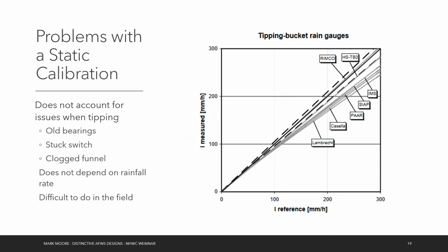There are some problems with static calibrations. For example, it doesn't account for the fact that you lose a certain amount of rainfall when the bucket's tipping. And so if you've got old bearings in there, it's not caring about how long it takes between tips. All it's caring about is how much rain does it take to tip. It's not going to tell you anything if your funnel's clogged or if you've got a stuck switch. A static calibration does not depend on rainfall.